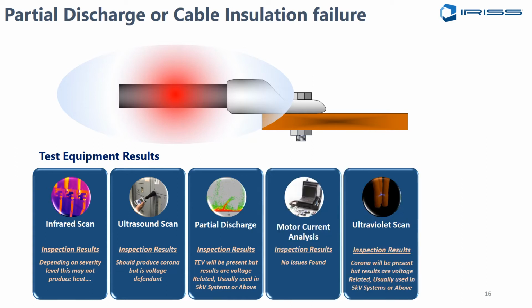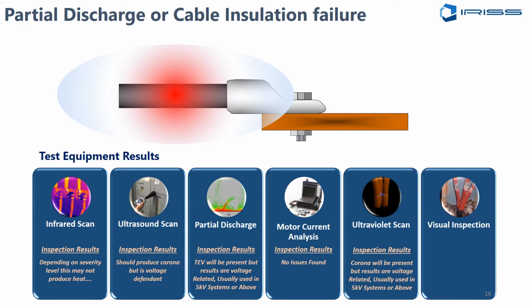Motor current analysis, we're probably not going to see much of. Ultraviolet scanning, yes, we will see something, again, over 5 kV. And then obviously the visual inspection is super important because the mechanical failures of partial discharge produce acids which produce residues, white residue, which a lot of electricians have seen. And this is very important to find, and it really underpins the importance of a visual inspection.